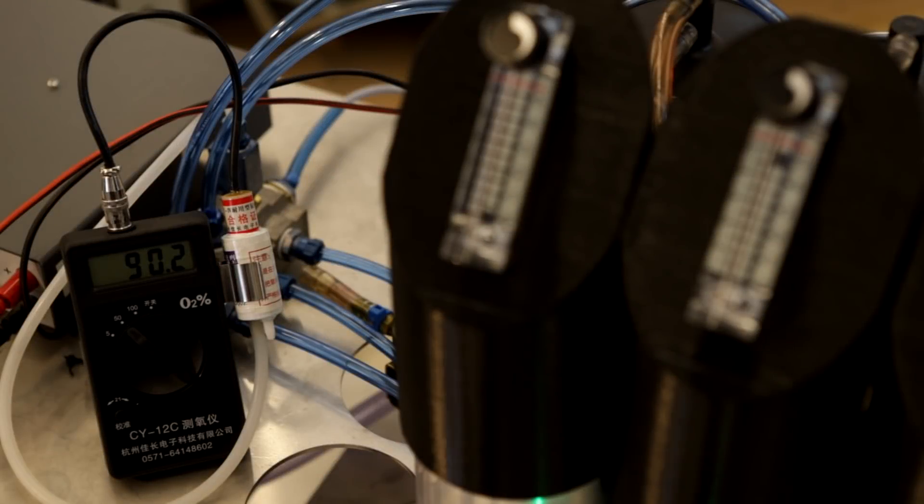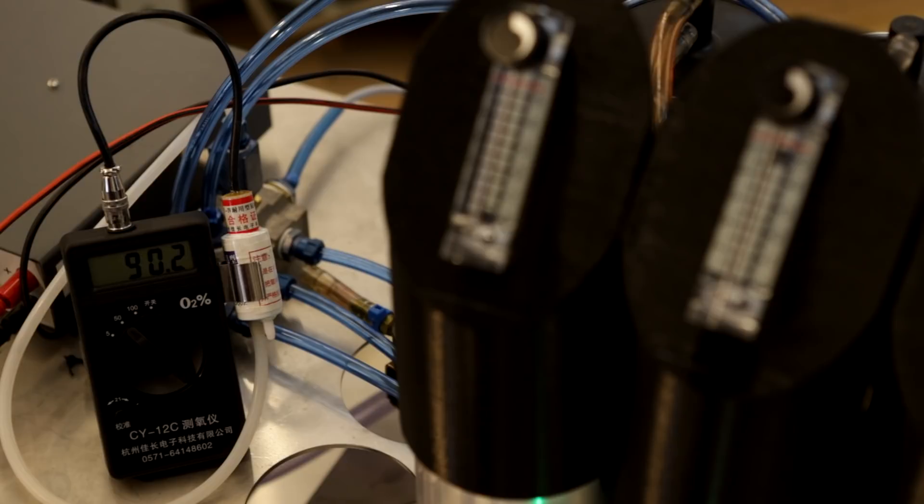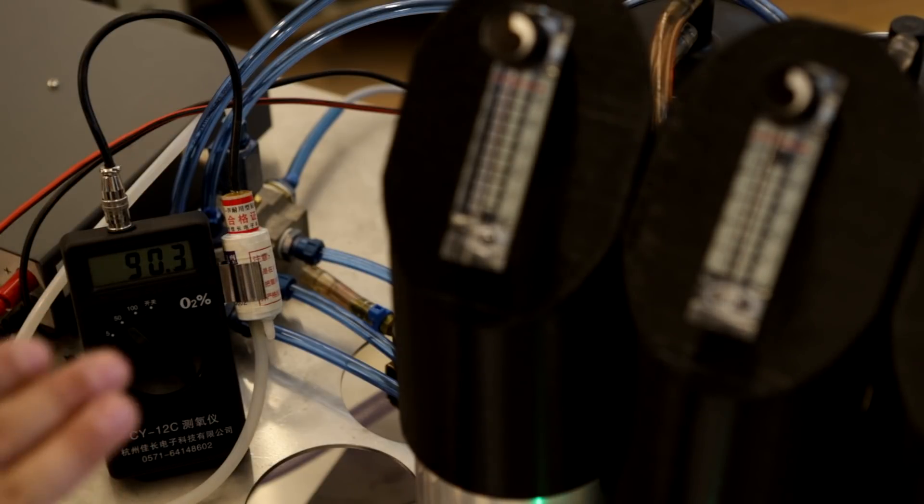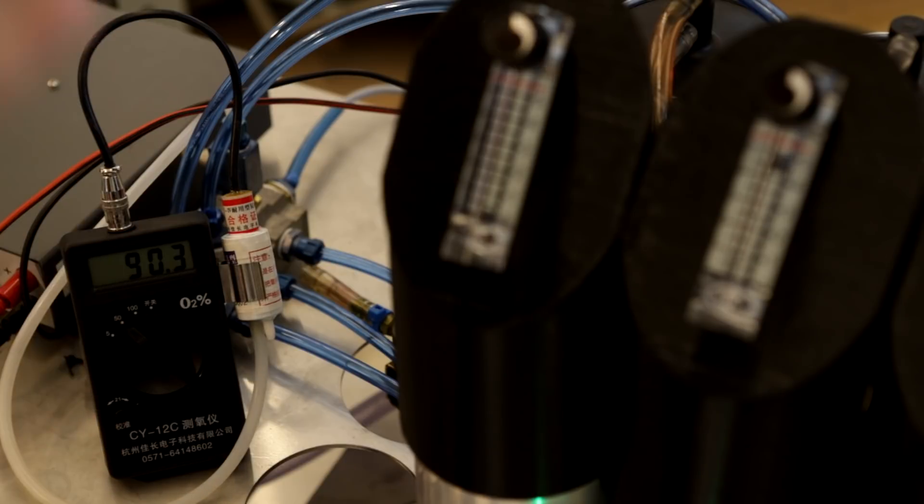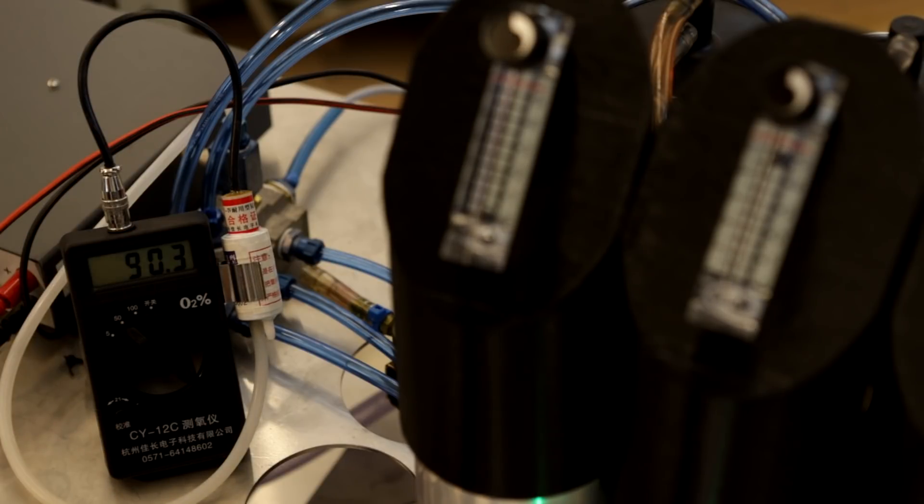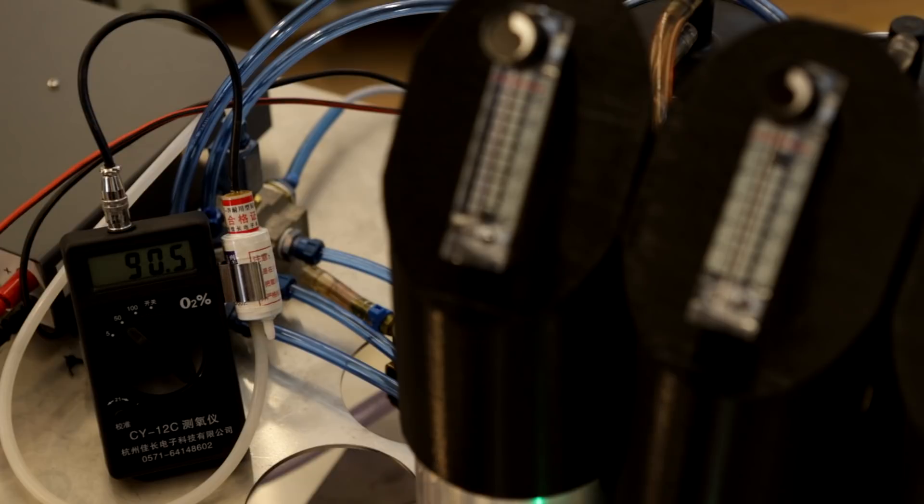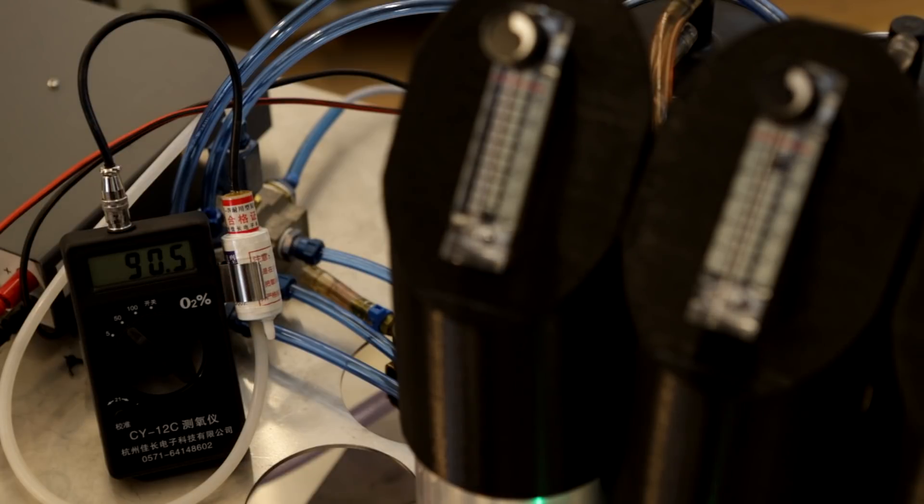We are over 90 percent already, and one thing that I realized, both cylinders work the same way, so you don't see the oxygen concentration going up and down. This is usually a sign of one of the cylinders working better and the other one working worse, like one is able to deliver higher concentration than the other one.